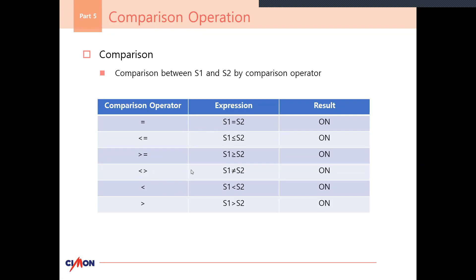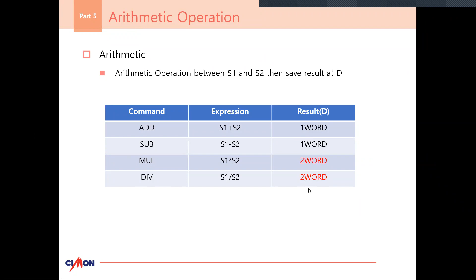Basic operators, but we do have them. We have add, subtract, multiply, divide. I recommend that when you do multiply and divide, you allocate 2 words open for the operation. So when you're programming your project, make sure you take into account that you're probably going to have to use 2 words for a multiply or divide operation, especially because the divide will take into account the whole string of characters that come out after the division.